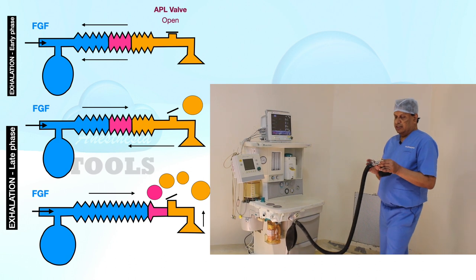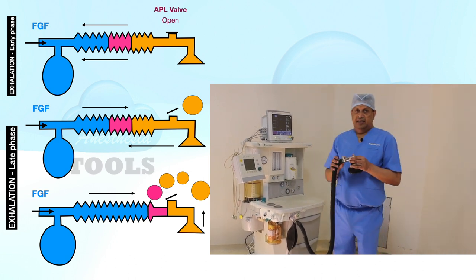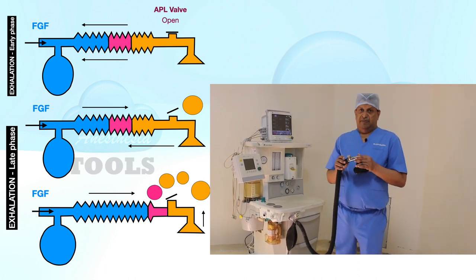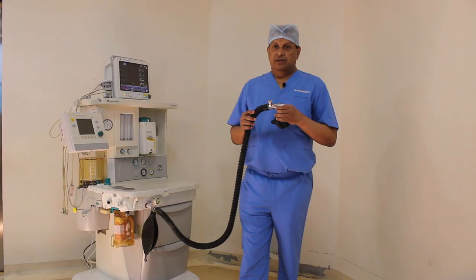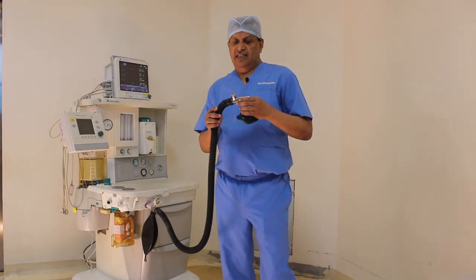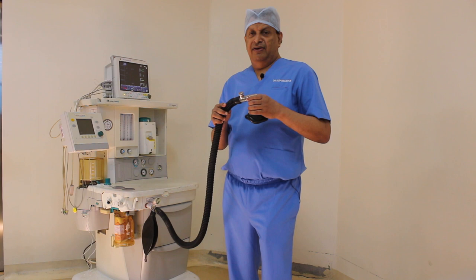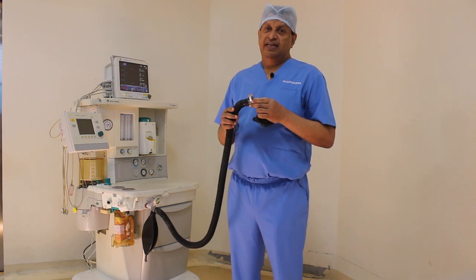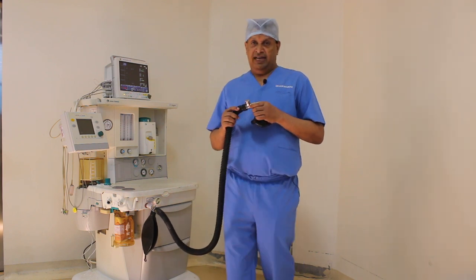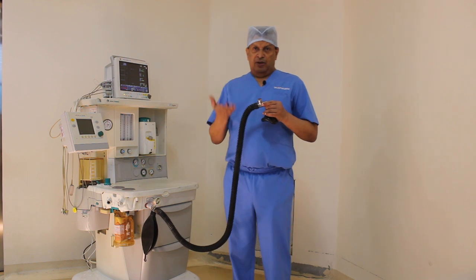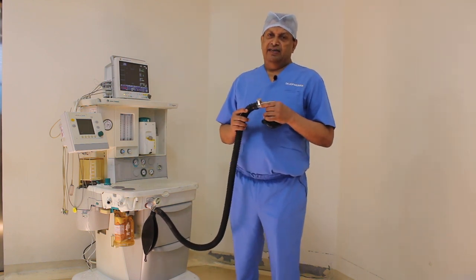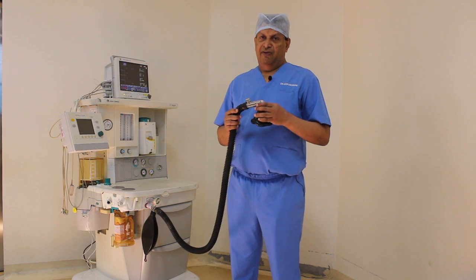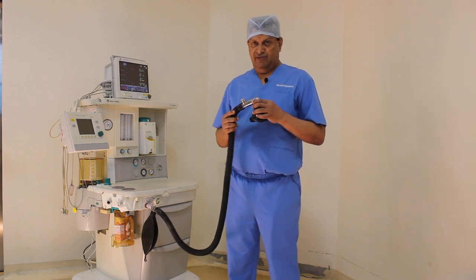This makes the Mapleson A system the most efficient system for spontaneous ventilation. Studies show that the fresh gas flow requirement during spontaneous ventilation is only the alveolar ventilation. To be on the safe side, we use minute ventilation as the fresh gas flow requirement for the Mapleson A system during spontaneous ventilation.